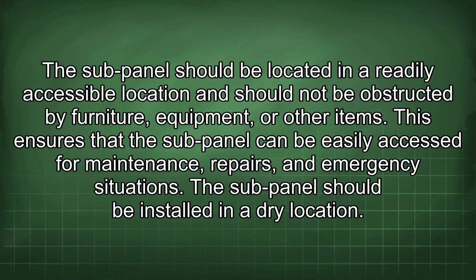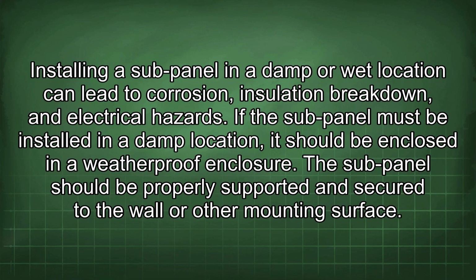The sub-panel should be located in a readily accessible location and should not be obstructed by furniture, equipment, or other items. This ensures that the sub-panel can be easily accessed for maintenance, repairs, and emergency situations. The sub-panel should be installed in a dry location. Installing a sub-panel in a damp or wet location can lead to corrosion, insulation breakdown, and electrical hazards.